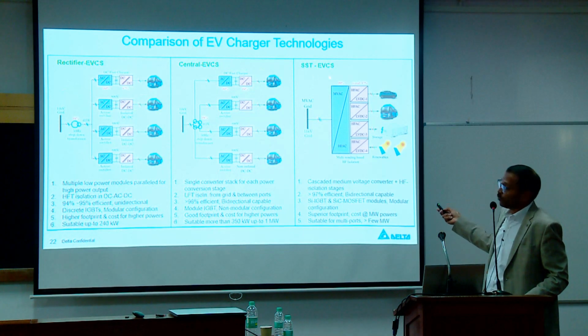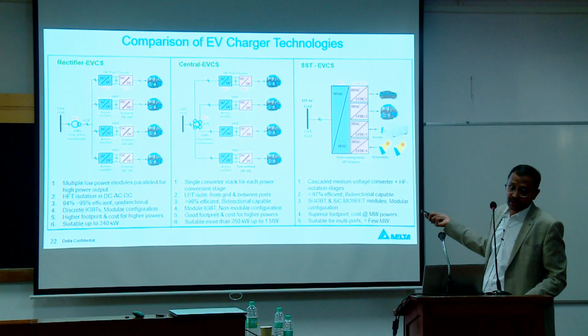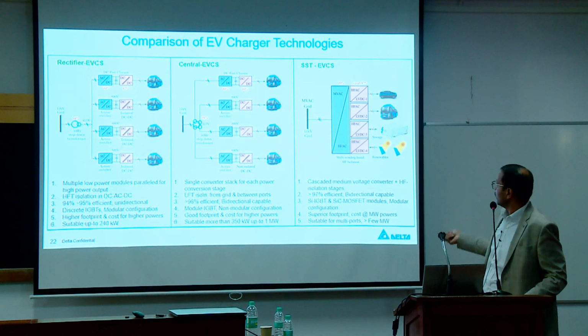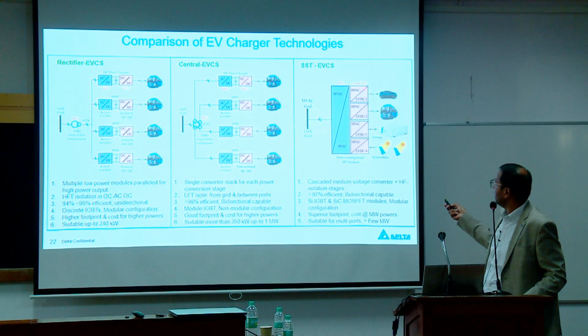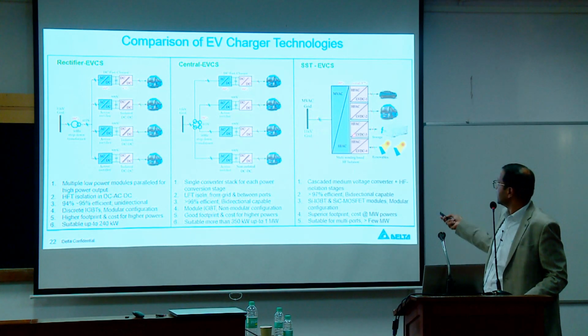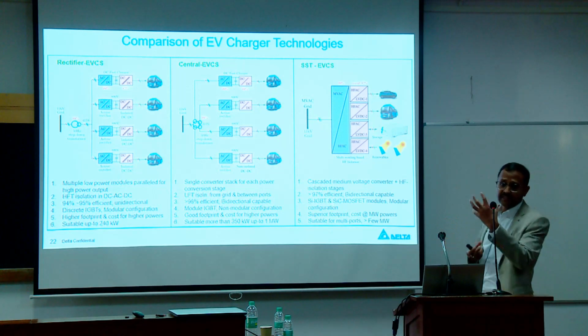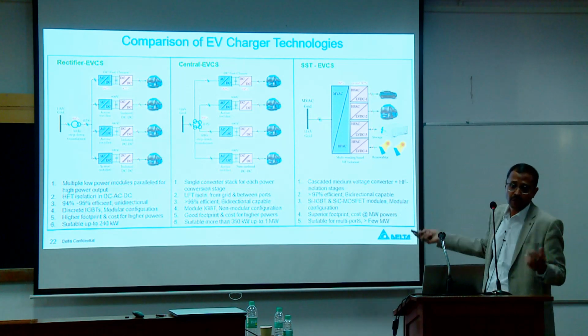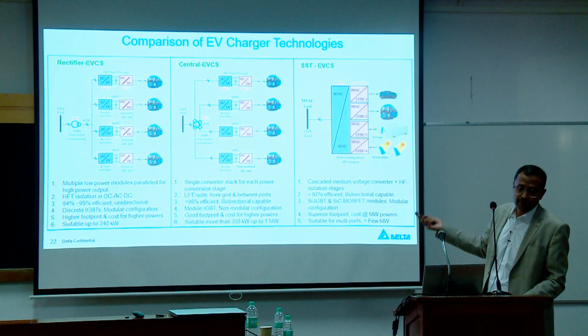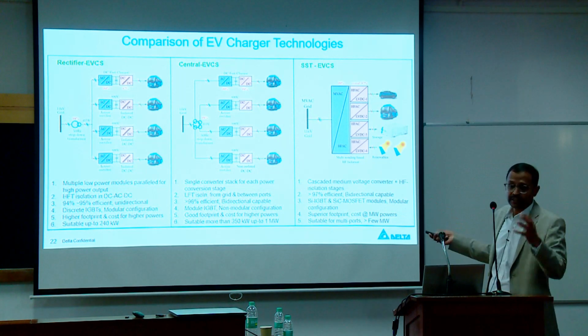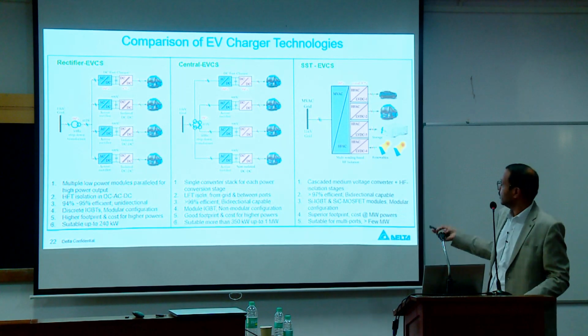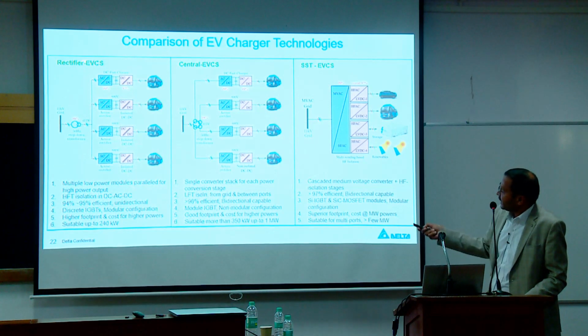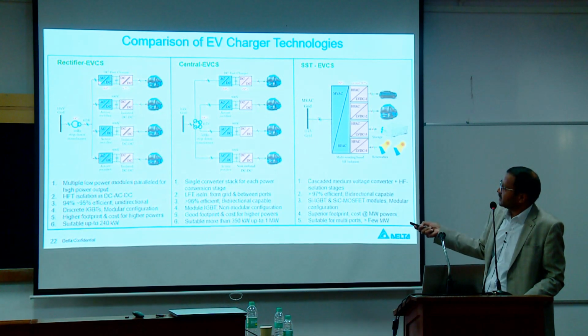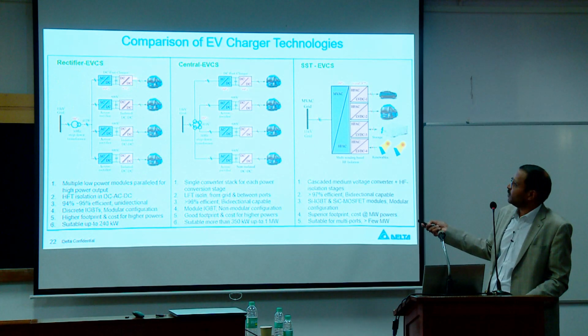The most efficient one would be SST based technology, solid state transformer based philosophy. You take 3-phase grid and make DC. Isolation is done with a single transformer here, a coupled transformer for however many outputs you want. If you want 4 outputs, you use 4 isolations with 4 windings, or 5 windings on one transformer. This is the most popular right now because it has evolved much faster and you have programmability.